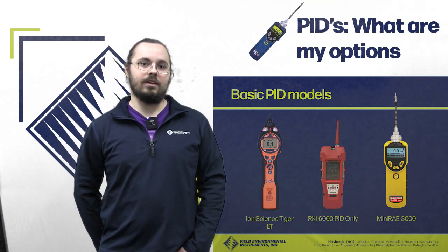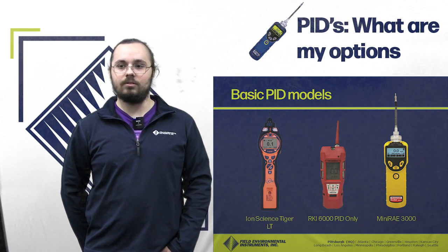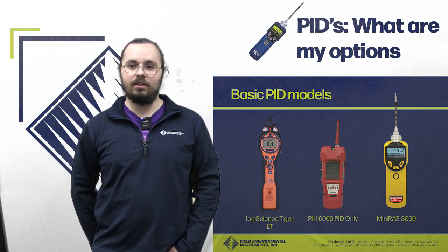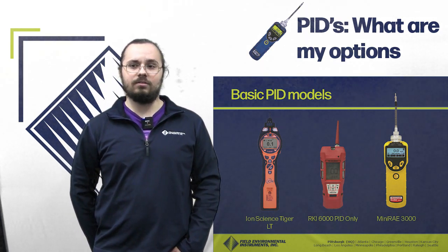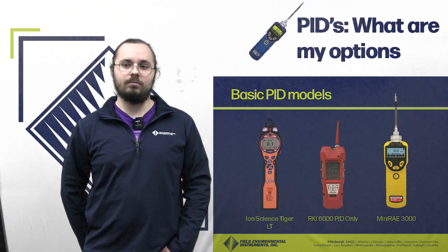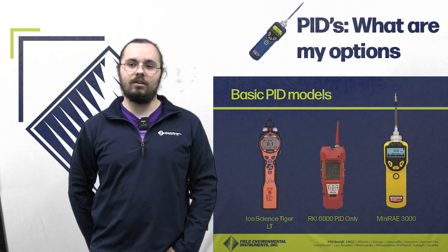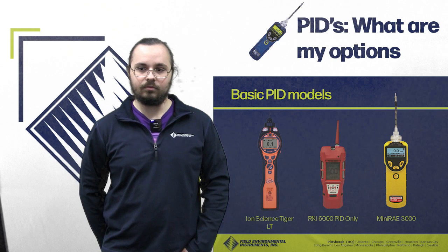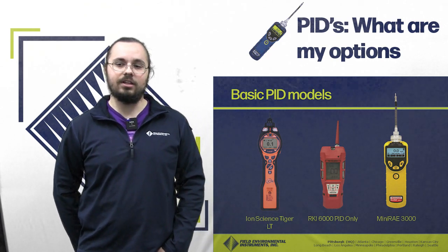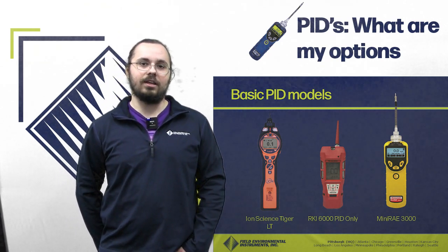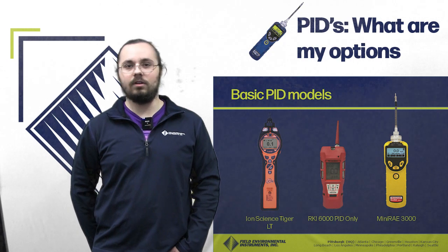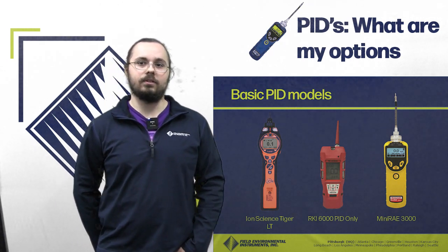The MiniRAE 3000, as you guys are probably most familiar with, has a range from 0 to 15,000 ppm with a resolution of 0.1 ppm up to 1,000 ppm. It has data logging features and typically uses a 10.6 eV or 11.7 eV lamp.